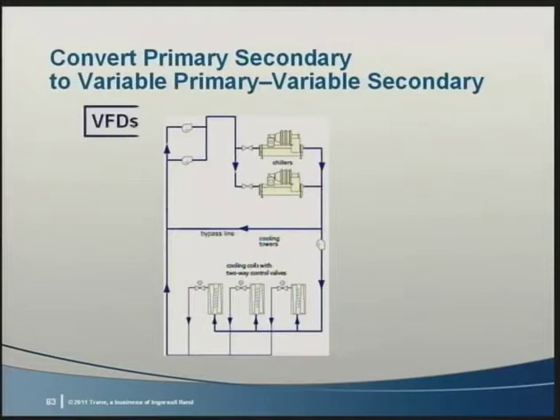With that said, many times a full chilled water system replacement is either untenable or way out of budget. What's another alternative? How about converting from primary-secondary to variable primary, variable secondary? Fewer changes need to be made, and they're much less invasive. For our example, we're going to start with primary pumps that are manifolded. First, add a VSD to the primary pumps, and while you're at it, open the balancing portion of the triple duty valve wide open and use the VSD to balance the flow rate and set the maximum pump speed. You'll likely save energy just by doing that.